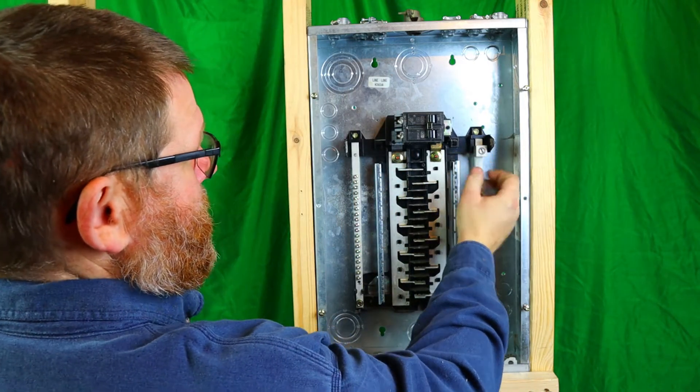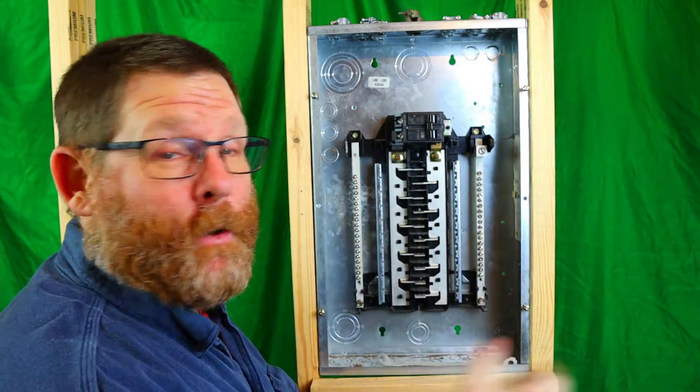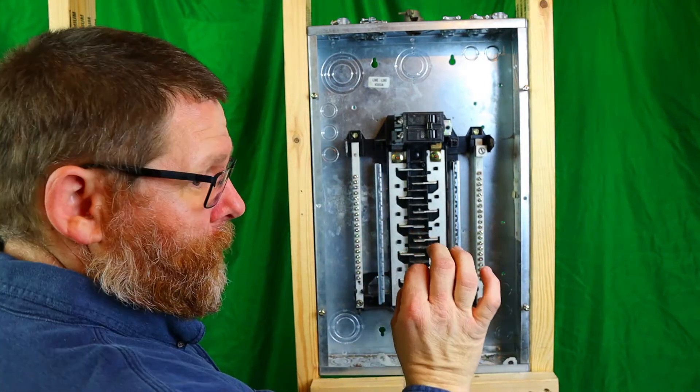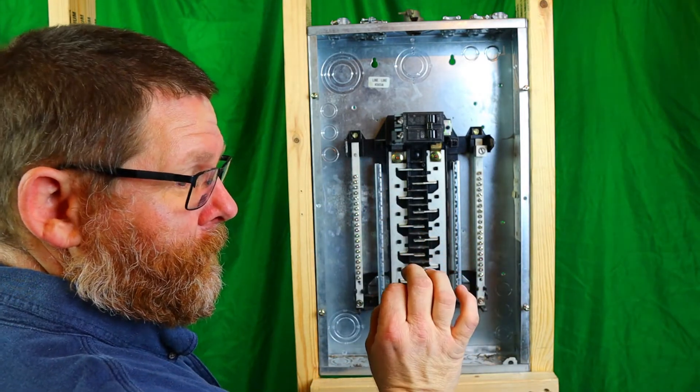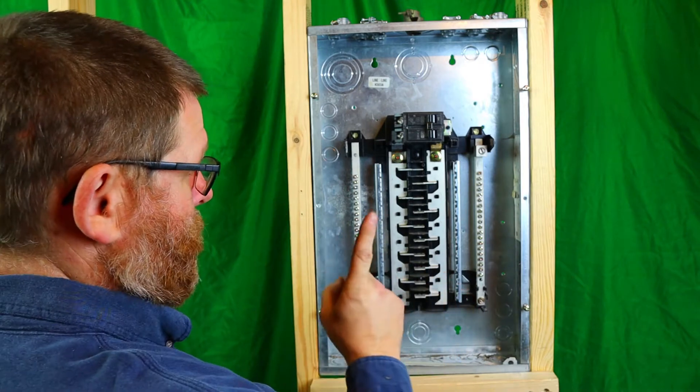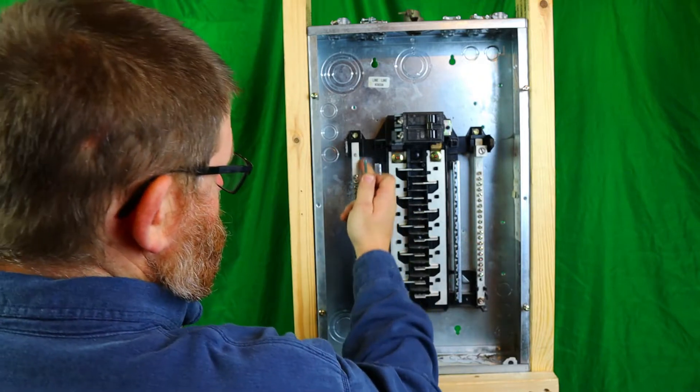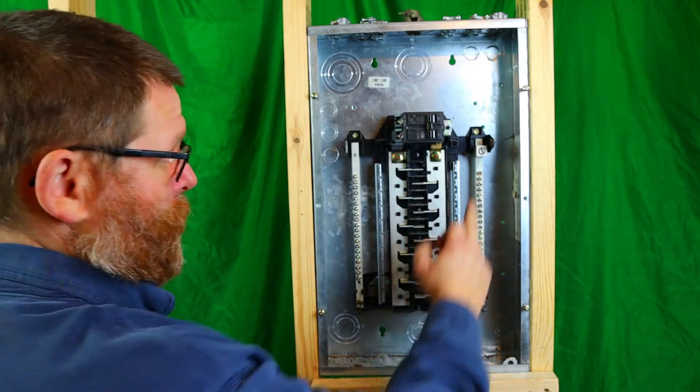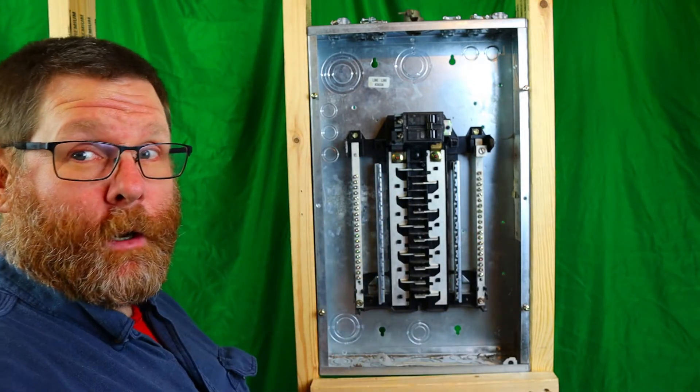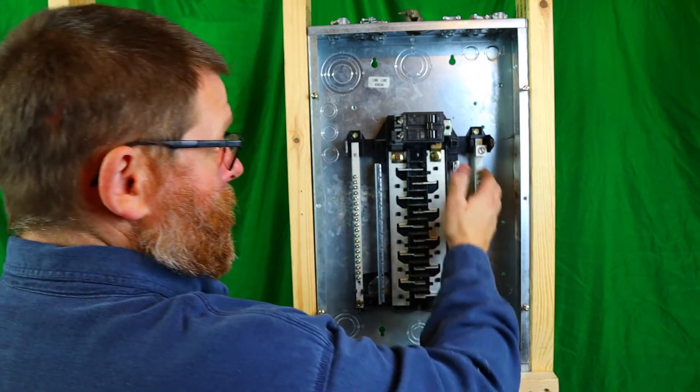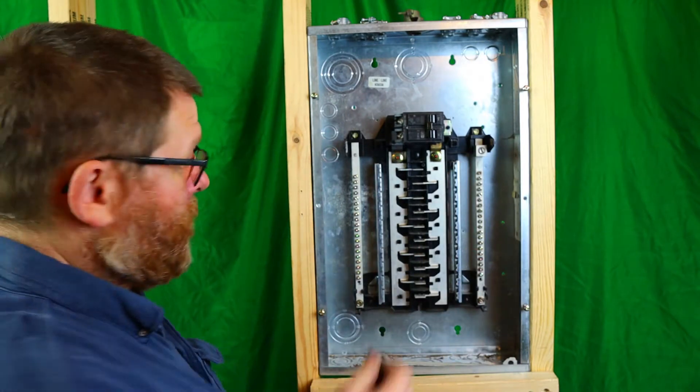So this is your neutral, and this could be over here - it doesn't really matter. But what matters on this panel is you have to bond the ground side. You do not bond the neutral. So this is going to stay non-bonded.